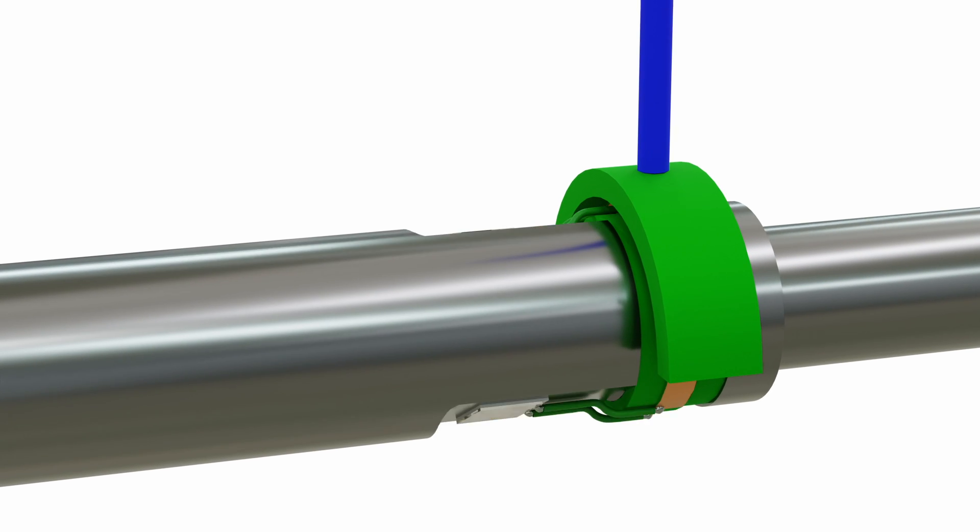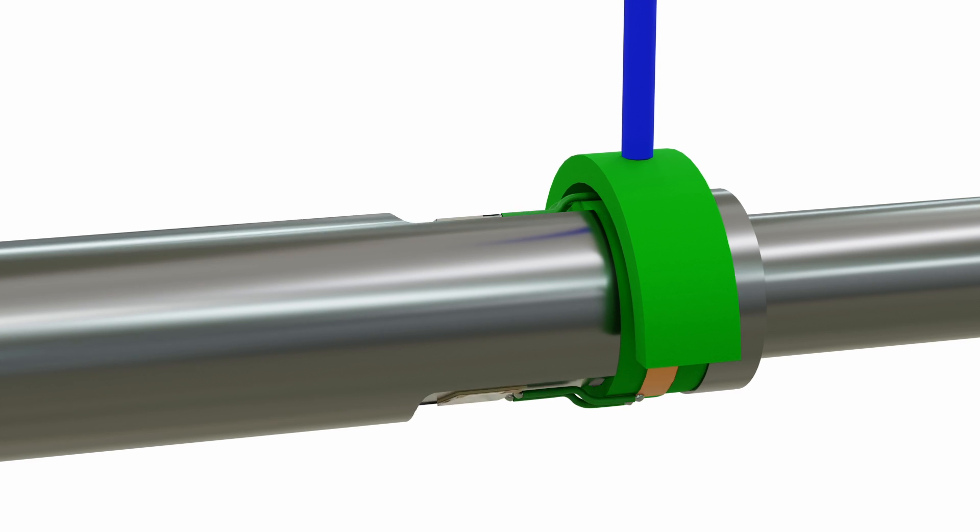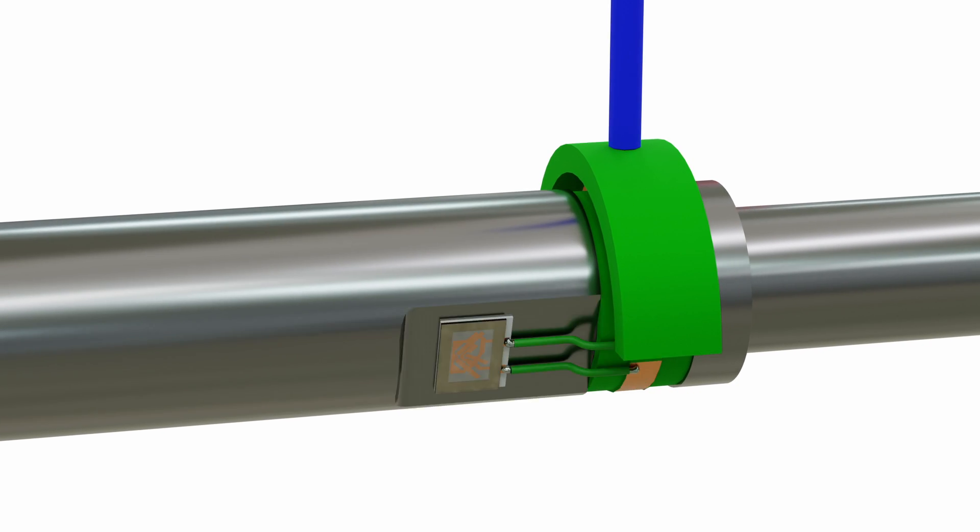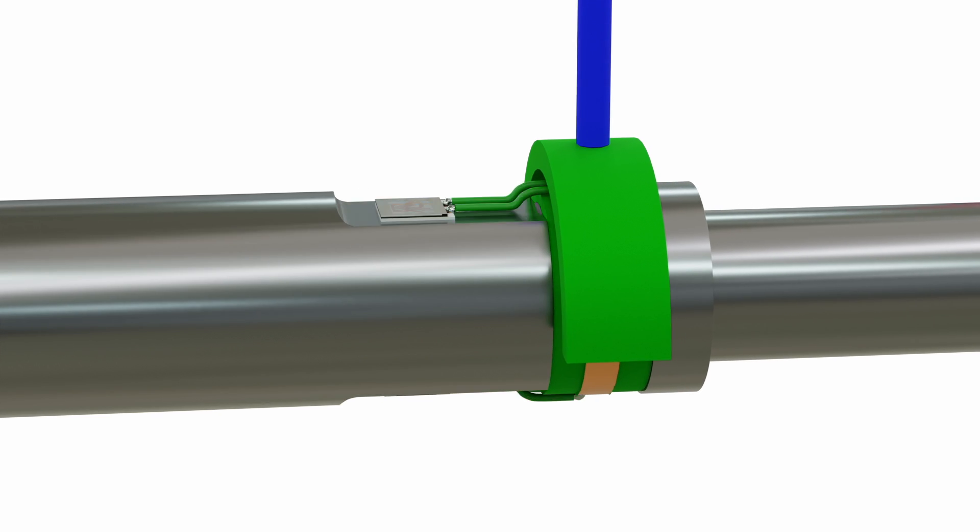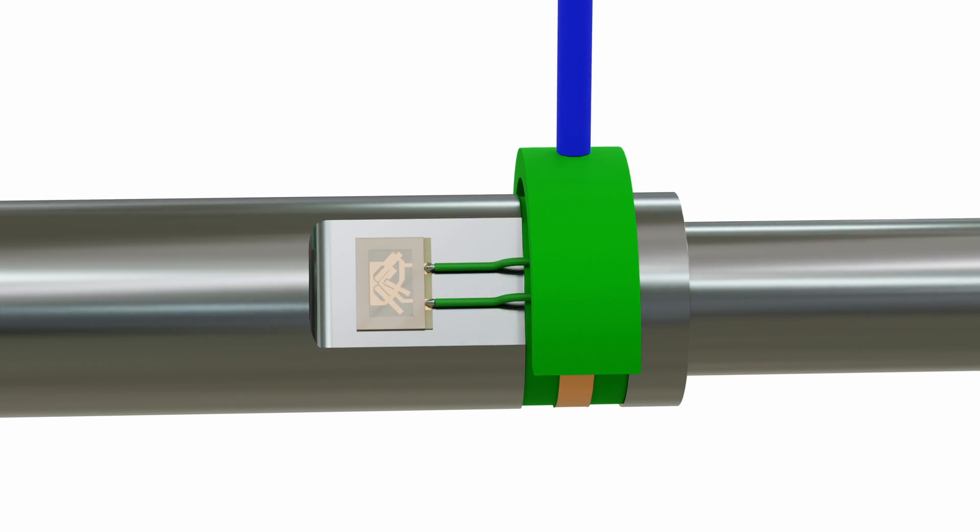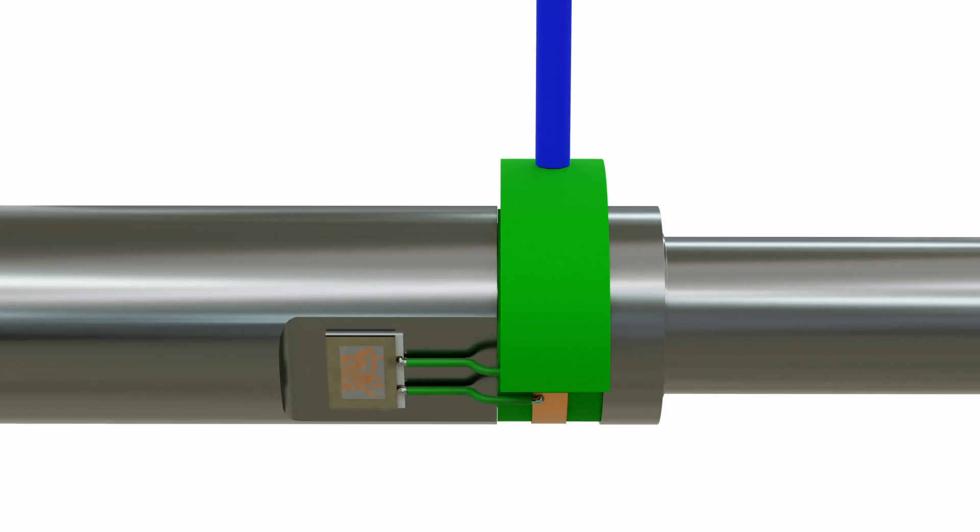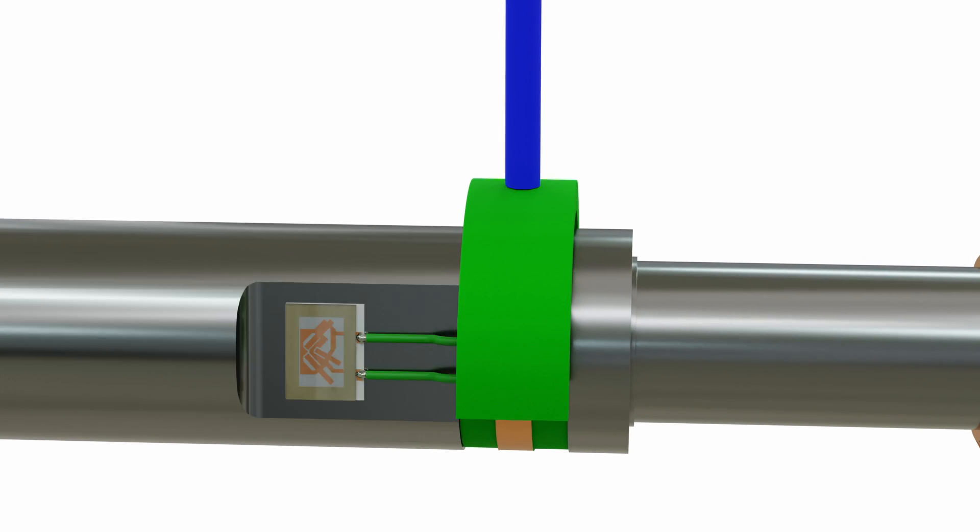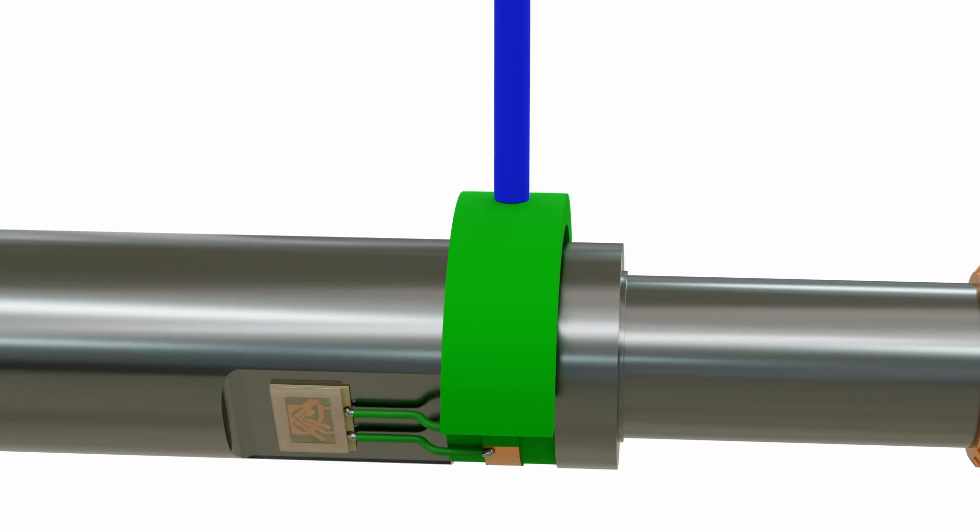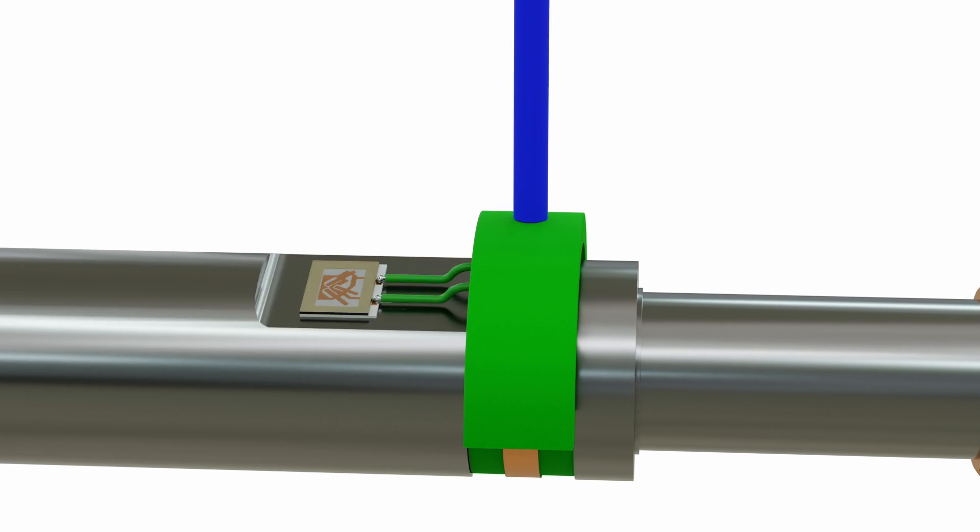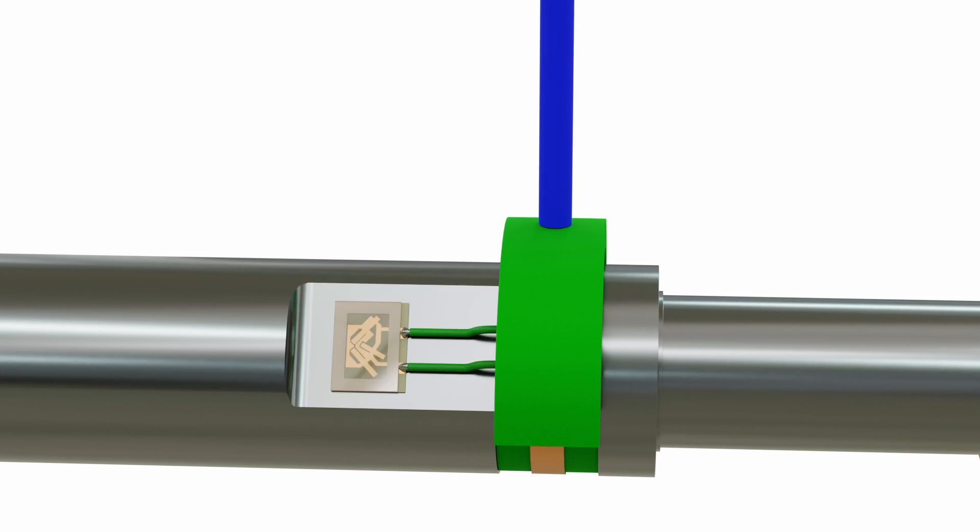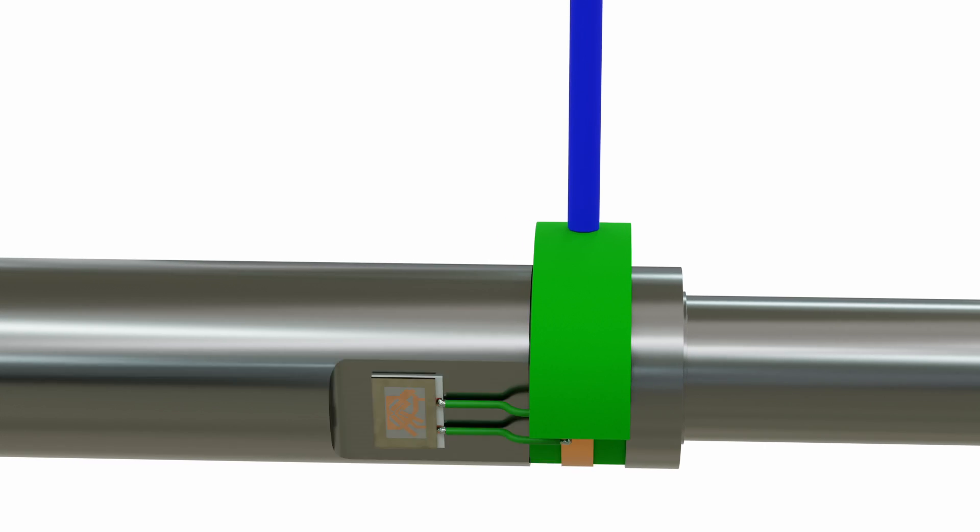The reader launches the interrogation signal, which is picked up by the sensor's antenna. The sensing element does not contain any DC power source and works as a passive backscatterer, reflecting the interrogation signal back to the reader. The backscattered signal reflects the frequency of oscillation affected by a physical measurement, such as strain and temperature. The reader analyzes the received backscattered signal and calculates the value of the physical measurement.